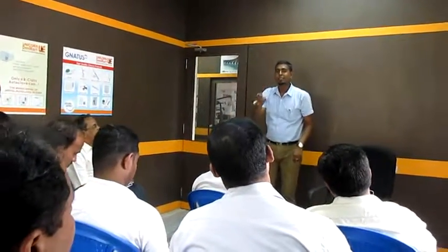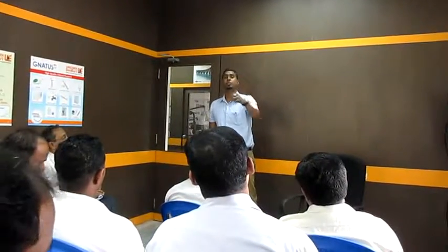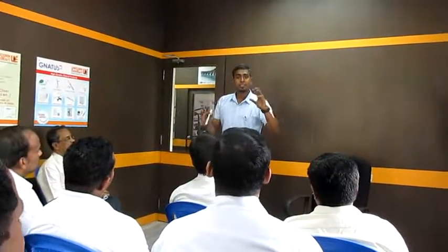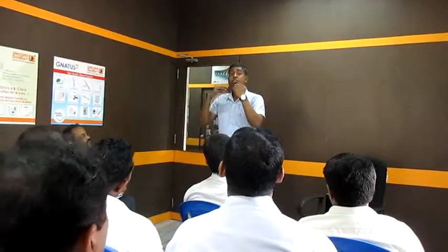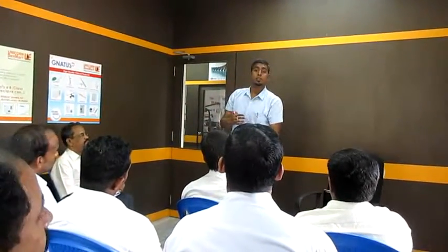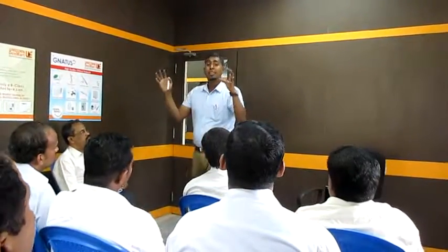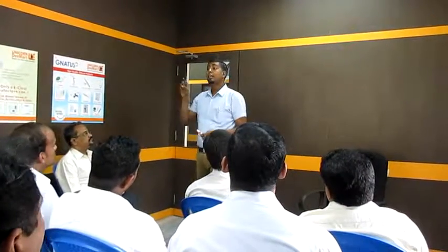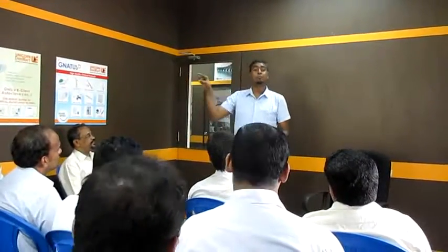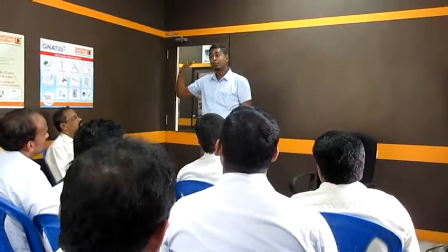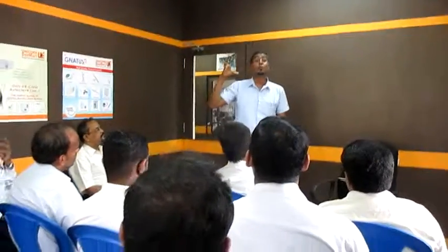These 5 parameters are vulnerable to change over a period of time. That is why in older machines you need to keep more exposure time. As the X-ray machine gets old, you need to increase the exposure time. Ultimately, by increasing the exposure time, what are you increasing? You are increasing the dose.